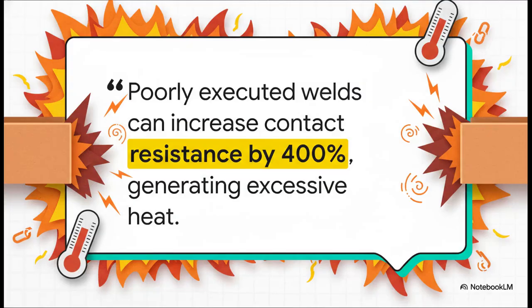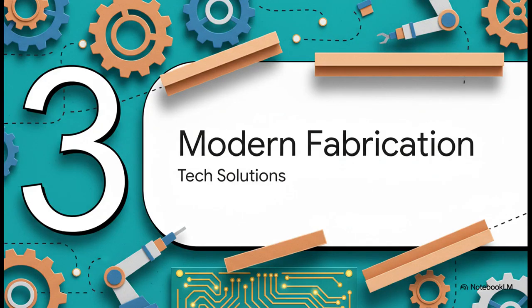Now, joining sections of busbar together, that's another huge hurdle. And this data from Siemens is just staggering: a single bad weld can crank up electrical resistance by 400%. That resistance generates an incredible amount of heat, creating a super dangerous failure point and dramatically shortening the system's lifespan. Okay, so the stakes are clearly sky high.